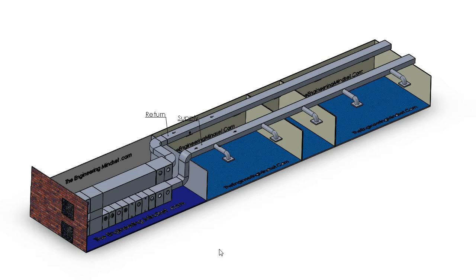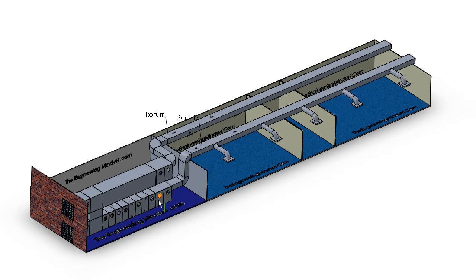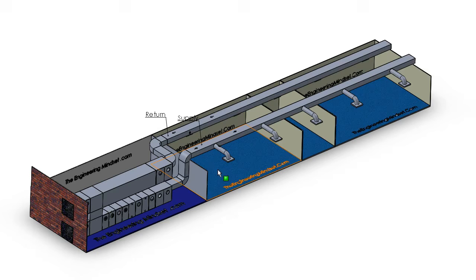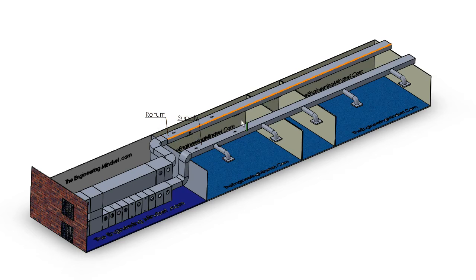Looking at the CAV system, here we've got a simple model of a small office. We've got the AHU located within the plant room. Then we've got the supply duct bringing all the fresh air that's being treated through various parts in the AHU, and that's being sent off along this main duct and then branching off into these diffusers. The air is then circulated around the room and that pushes all the dirty used air back up into this grill, collected in this duct, and returned back to the AHU where it can either be dispersed out to atmosphere or some of it can be recycled and reused.